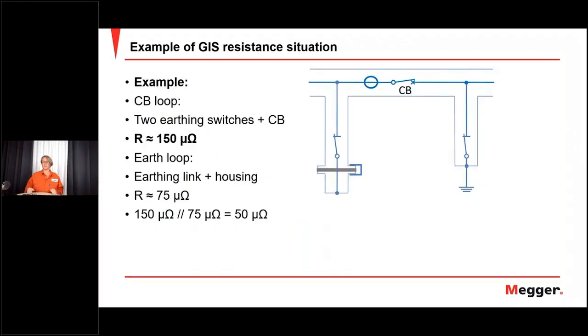And I wanted to show you here an example. Here you have a circuit breaker up in the middle, you have a current transformer, and you have a bus bar at the top. And here it's all enclosed in the big enclosure, so you can't access here. You have the grounding points here and here, and you have the isolated grounding point here. And if you measure this circuit breaker with dual ground and compensate, you will have 150 microohms. From this point to this point.